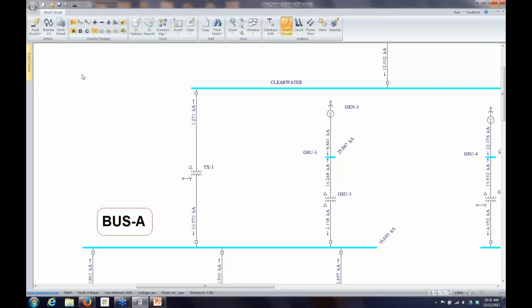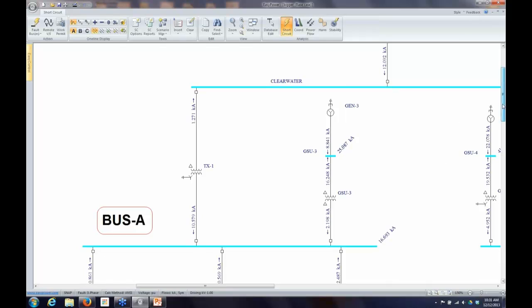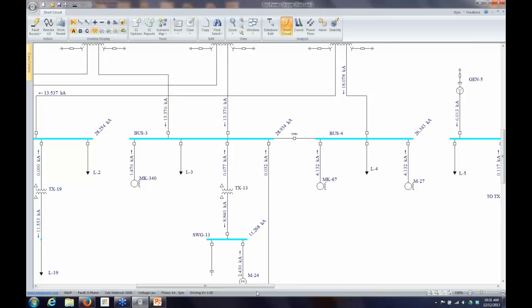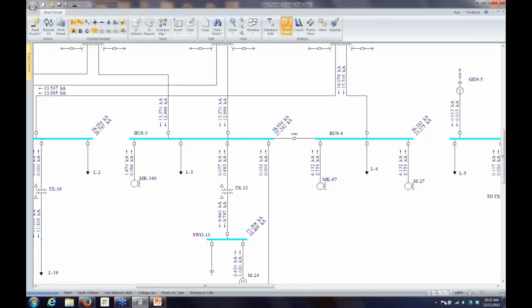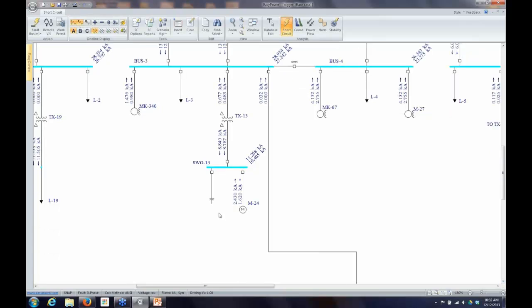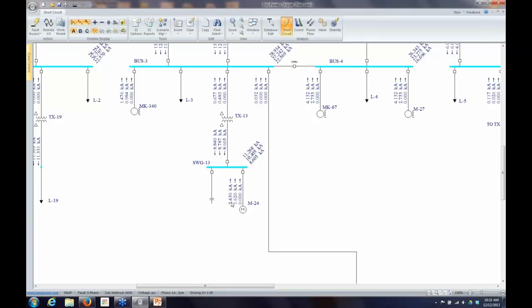The program solves three different networks because motor contributions decay over time depending on the size and type of motor. Looking at an induction motor example: the half cycle maximum contribution is 2,400 amps, at five cycles it's 1,620 amps, and at 30 cycles it's zero. By 30 cycles, motors will no longer be contributing fault current, which reduces the total fault current at that time snapshot.